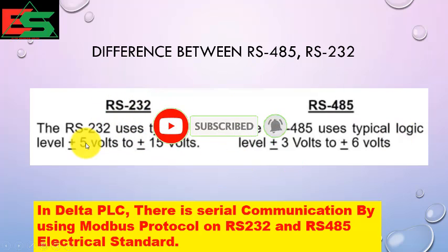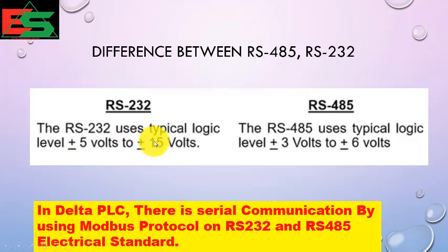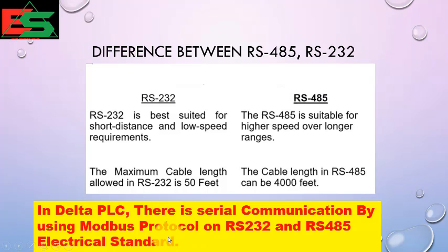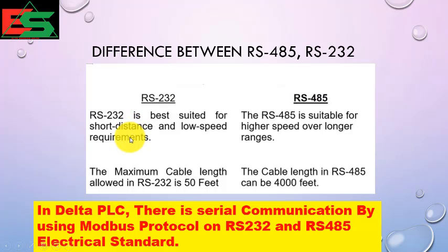In RS-232 the voltage range is plus/minus 5 to plus/minus 15 volts. But in case of RS-485 it is plus/minus 3 to plus/minus 6 volts. In Delta PLC there is serial communication using Modbus protocol on RS-232 and RS-485 electrical standards. RS-232 is very good for short distance, like communication between a PLC and a PC, so mostly we use RS-232 for that.